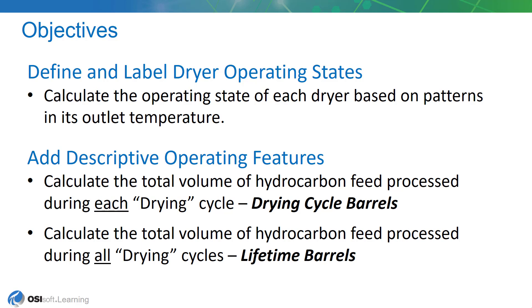Secondly, we'll be adding two descriptive operating features that have to do with the life of the drying bed. The age of the molecular sieve is really identified by how many barrels of feed it processes. The first feature, drying cycle barrels, will be the total volume of hydrocarbon fed during each drying cycle. The second, lifetime barrels, will be the total volume of hydrocarbon feed processed during all drying cycles.